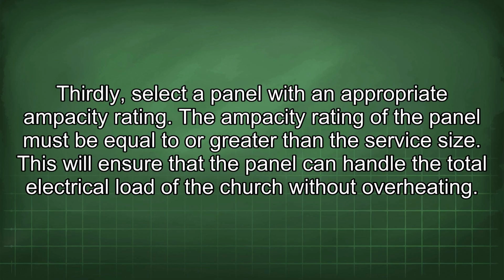Thirdly, select a panel with an appropriate ampacity rating. The ampacity rating of the panel must be equal to or greater than the service size. This will ensure that the panel can handle the total electrical load of the church without overheating.